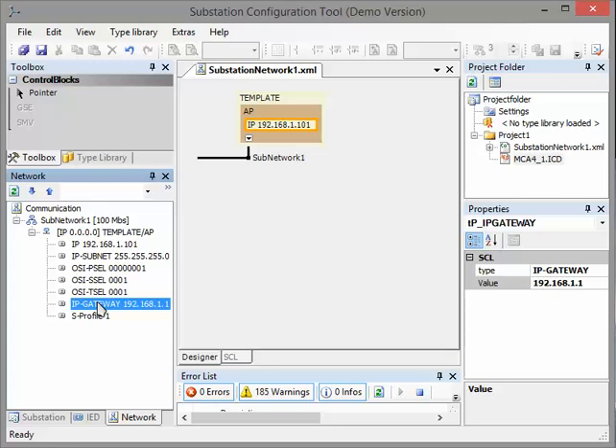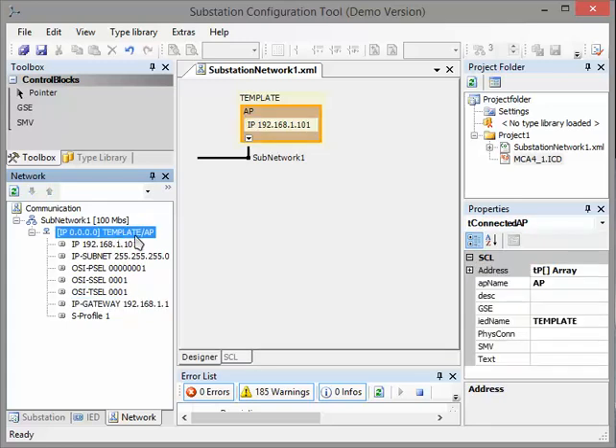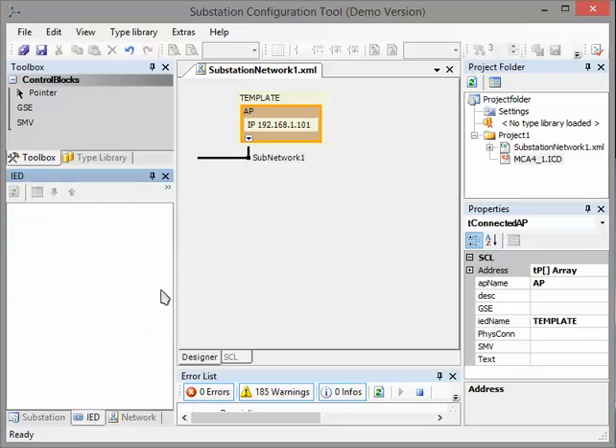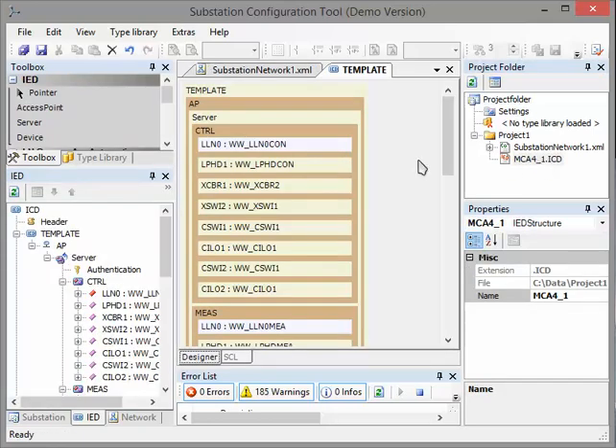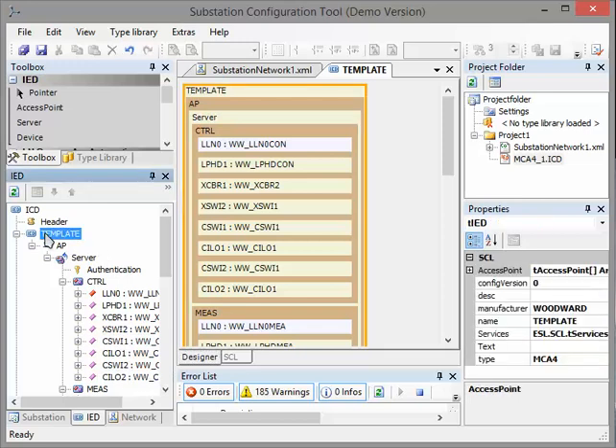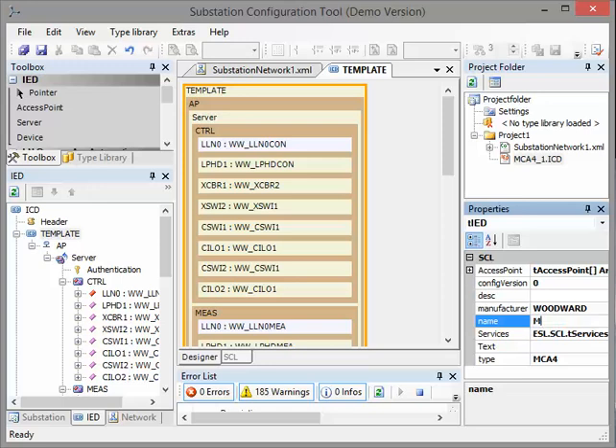The next step is that we change the name of our device, because 'template' is not a useful name — if you have five devices like this you will never be able to separate them. Please click on IED. Now we make a double click on MCA4 to open our file, and the complete structure opens. Now we change the name 'template' to 'MCA4_1'. We click here and enter 'MCA4_1'. Now the name of the device was changed inside of our substation configuration.